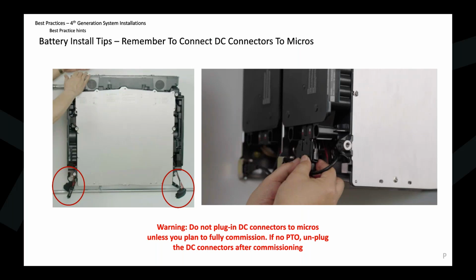Great question, and fair question honestly. The AC Sense is a 120 AC loop, okay? So what we currently do is we intercept the back feed with, like you said, a 100 amp disco, a 3-pole - that's your line 1, line 2 - and then we use a smaller wire to actually disrupt that AC Sense. What that does is it signals to the combiner to open relays, to put the batteries into an idle state, and signals to the roof.